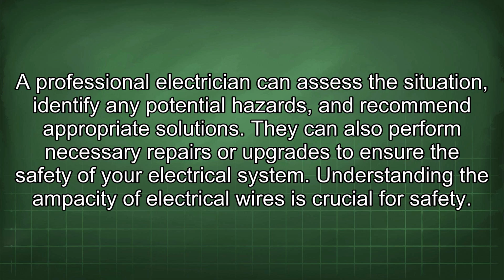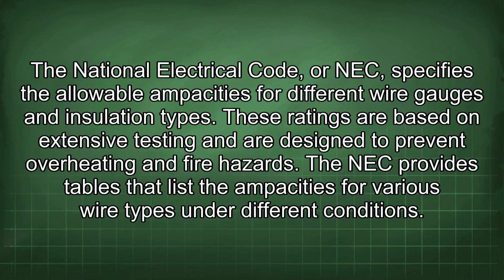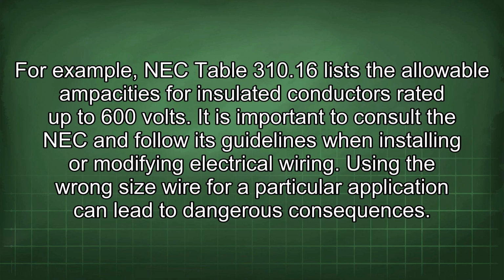Understanding the ampacity of electrical wires is crucial for safety. The National Electrical Code, or NEC, specifies the allowable ampacities for different wire gauges and insulation types. These ratings are based on extensive testing and are designed to prevent overheating and fire hazards. The NEC provides tables that list the ampacities for various wire types under different conditions. For example, NEC Table 310.16 lists the allowable ampacities for insulated conductors rated up to 600 volts.